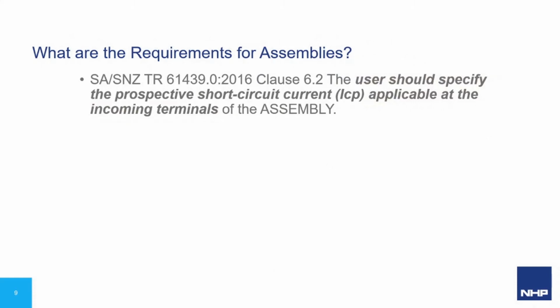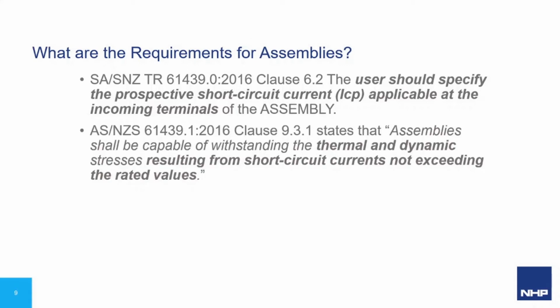Now that we have our specified maximum faults that can occur, we can move on to selecting appropriate equipment for our assemblies that is capable of withstanding the nominated fault, just in case the worst case ever occurs. AS 61439 Part 1, Clause 9.3.1 states that assemblies shall be capable of withstanding the thermal and dynamic stresses resulting from short circuit currents not exceeding the rated values.